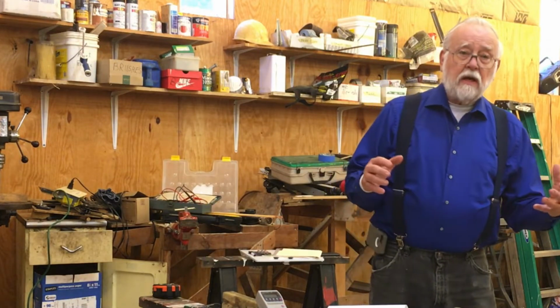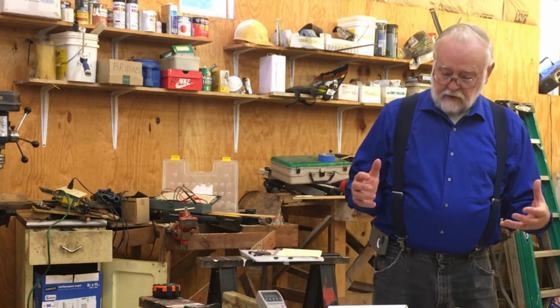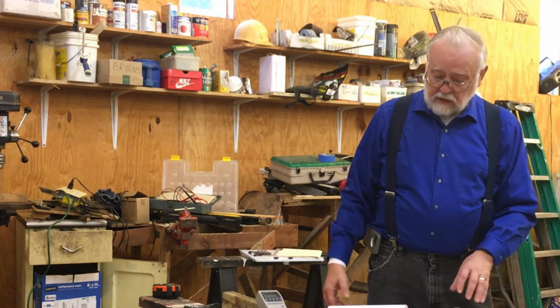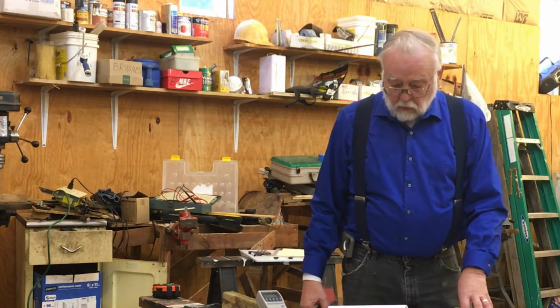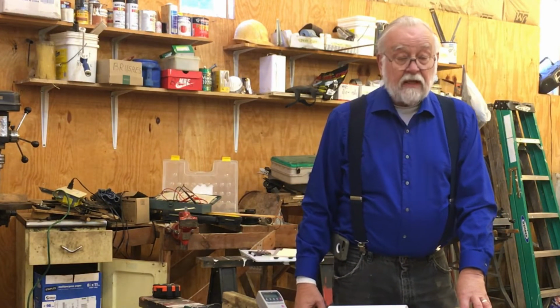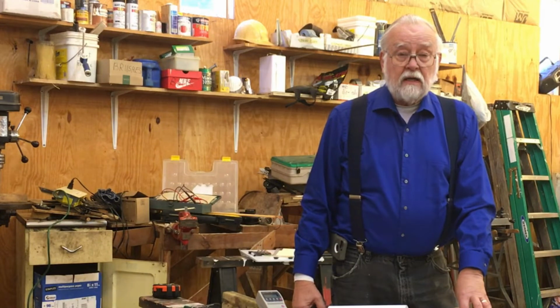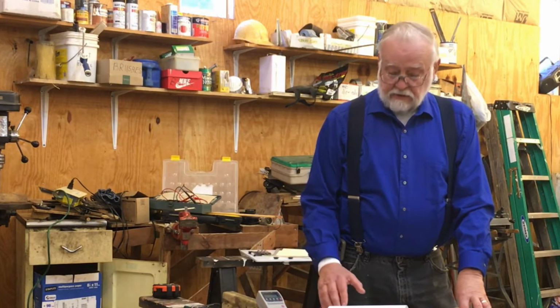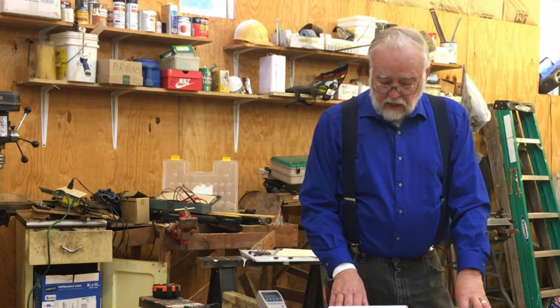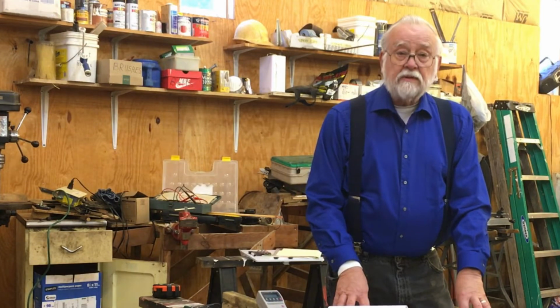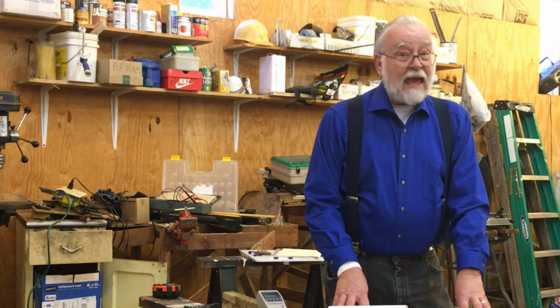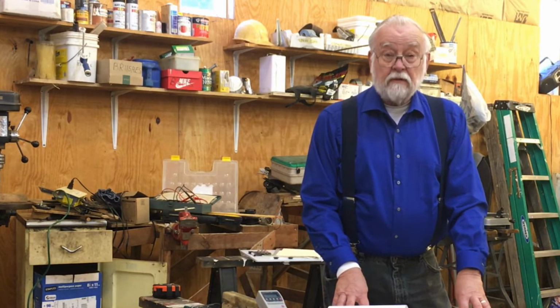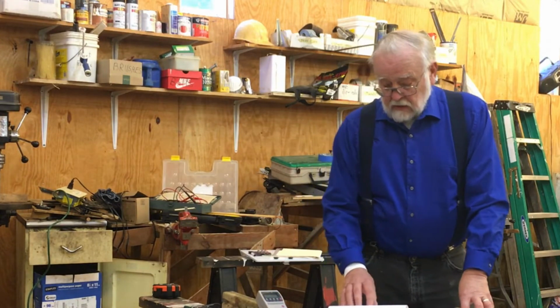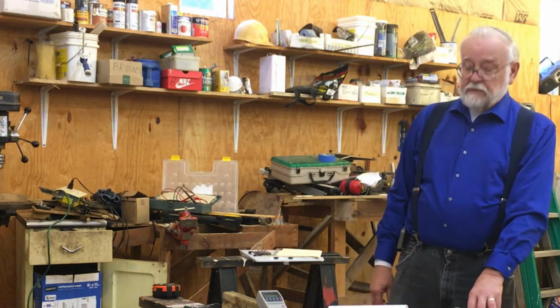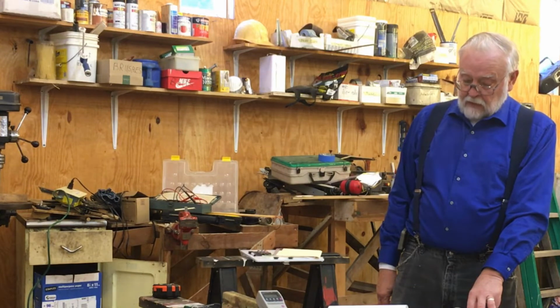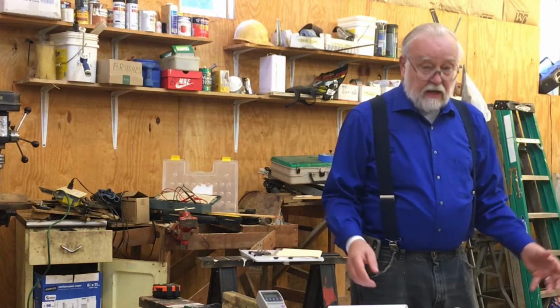Now my definition of the generator no longer being able to meet the requirements of the load is if, let's say, the voltage is not within 5 volts, or say 115 volts, and if the frequency of the generator is more than 3 cycles away from 60 hertz. So it's not good enough.